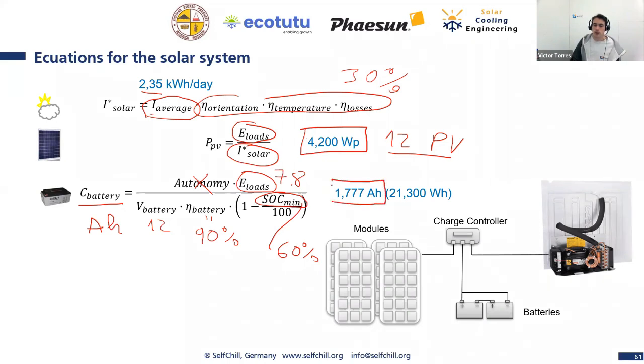1,700 amperes hours, which is 21 kilowatt hour of energy that we need to have in our batteries. So if we have batteries of 100 amps, we will need 17 batteries, which you can see is already a lot, right? A lot of battery capacity we need.